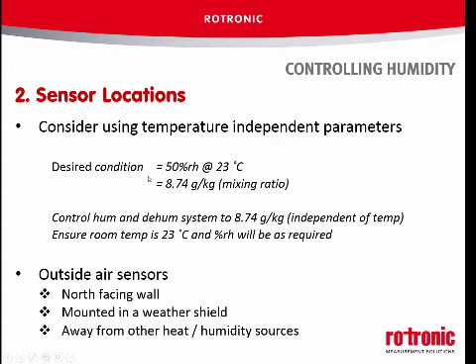And it's this idea of getting this absolute humidity window in the air handling unit and delivering that to the room, and as long as the room's at the right temperature, then we're going to be spot on with the humidity.